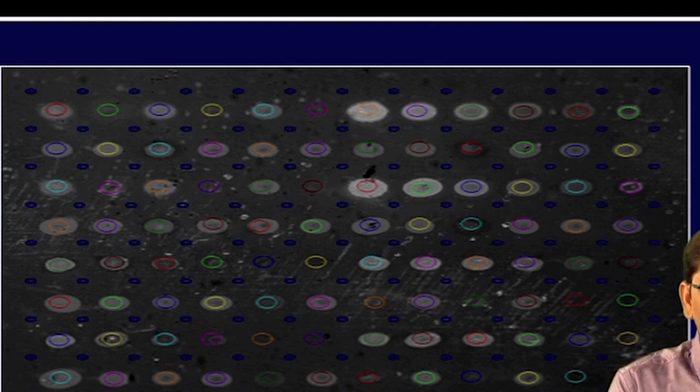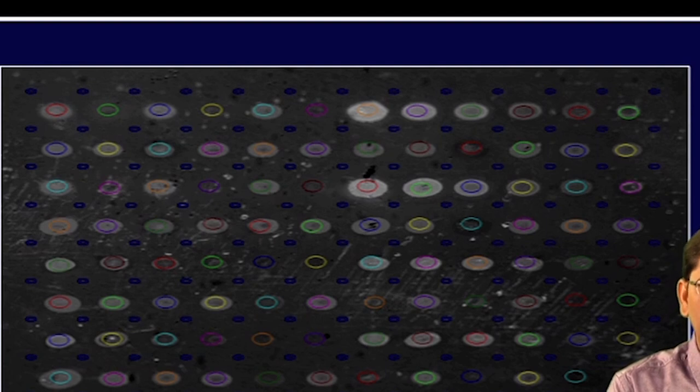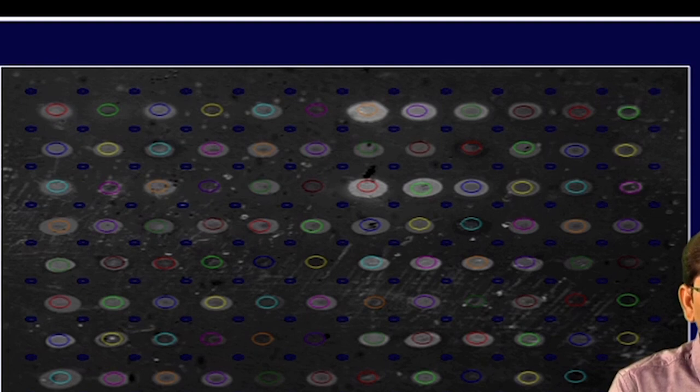Now, this image shows an SPRI image generated by a CCD camera, and the software adds some spots on the background surface. This is an image taken from a proteomic instrument, an SPRI imaging device. Each of the ROIs or region of interest can be defined as a region of interest for measurement. This software generates some spots on the background which are automatically generated. So, surrounding each protein spot, four background spots are generated, which can be used for background subtraction for the protein or biomolecule which is printed.